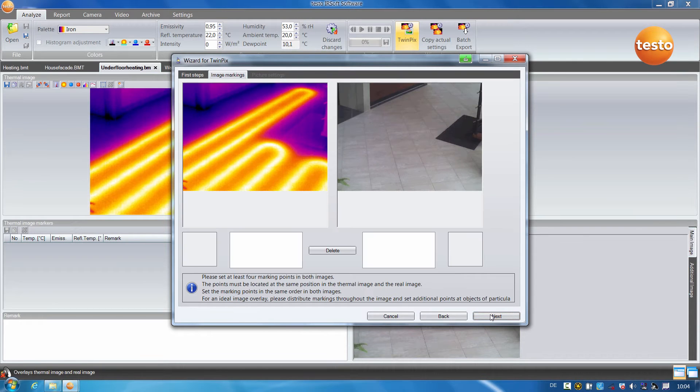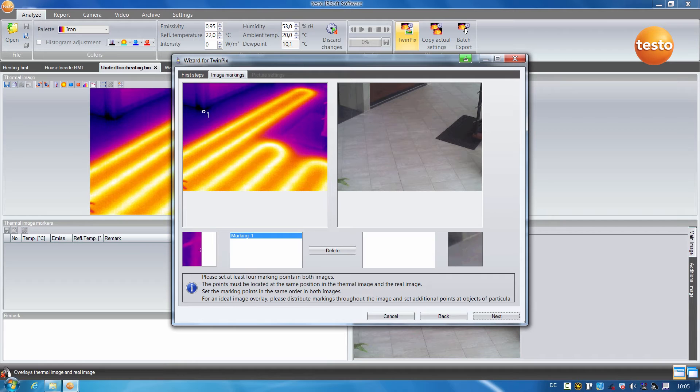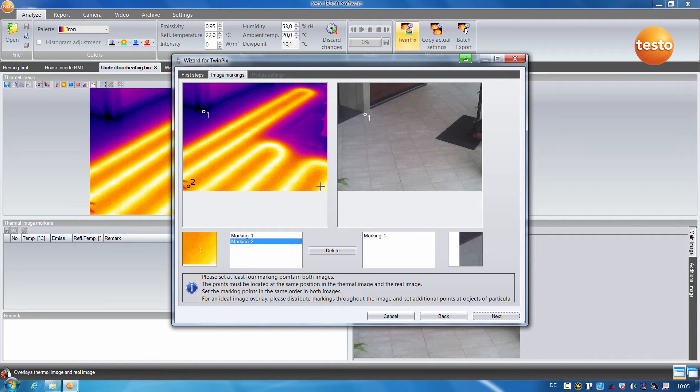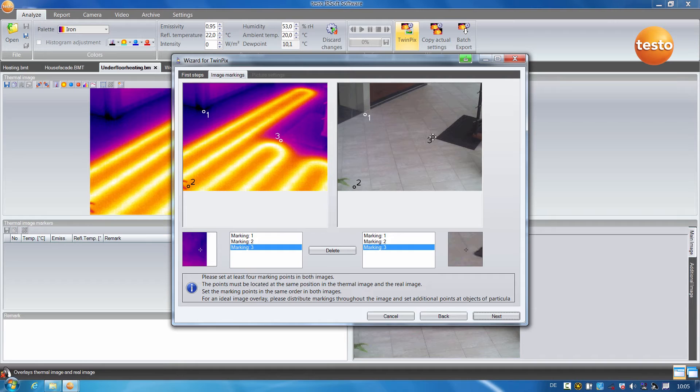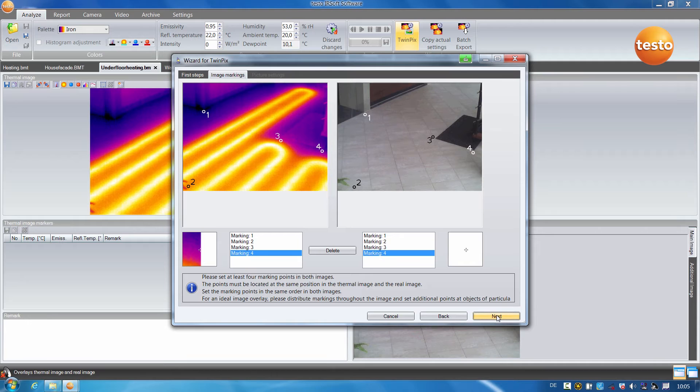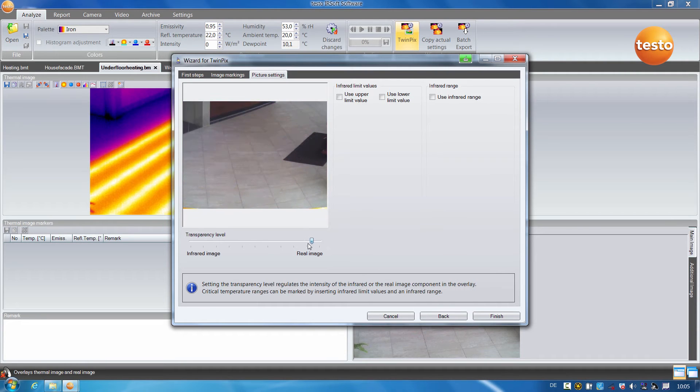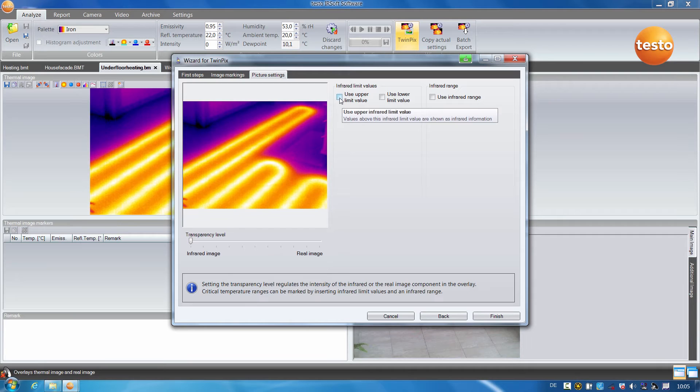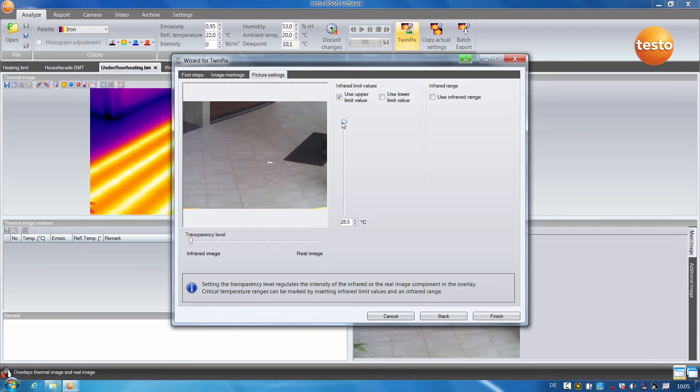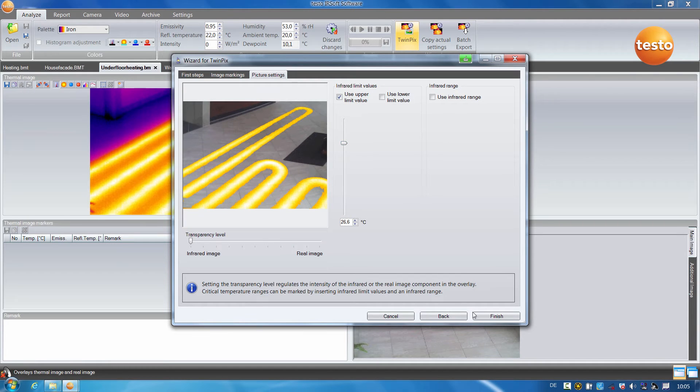For the overlay, four identical markings are made in the thermal image and the real image. I can then set the transparency level between the real and the infrared image and can color the upper temperature limit values. Here you can see very well where the underfloor heating is situated in the tiled floor.